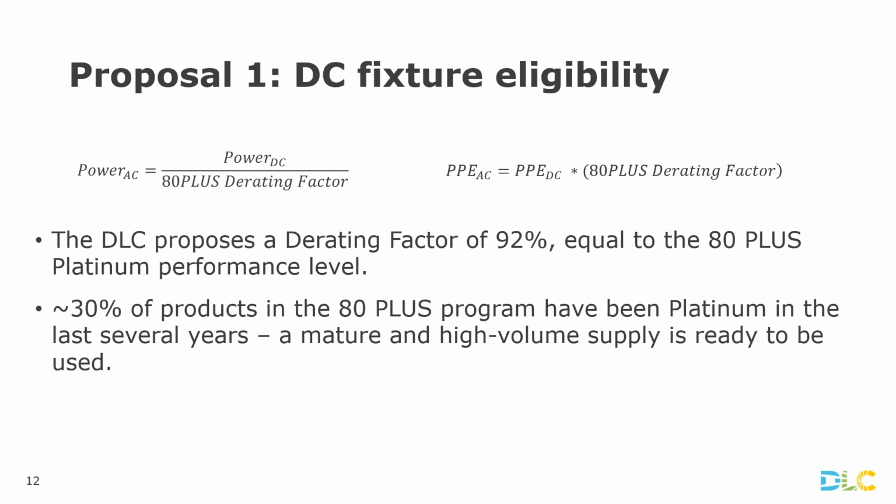And again, this is important to note, at that 20, 50, 80, and 100% performance level of load, which is important if you're thinking about a one-to-many power supply to fixture setup, in which you may not be certain as a utility or an end user how many downstream devices are going to be coming off that power supply. So the result of this is that we feel that there is a large and mature global supply of products that can be plugged into this with minimum disruption, and we think great outcomes for the end users.